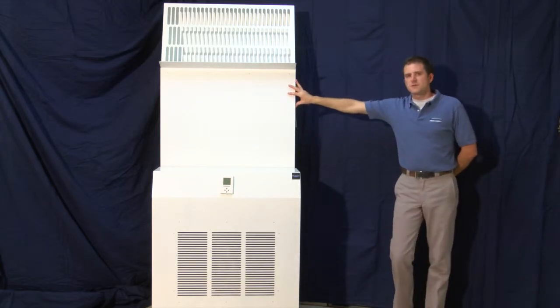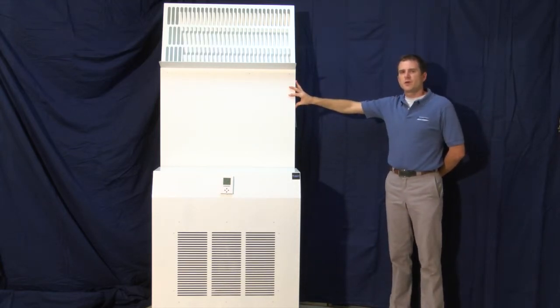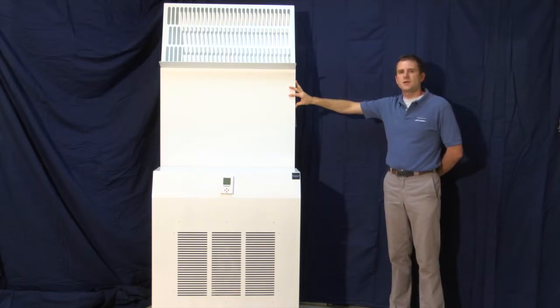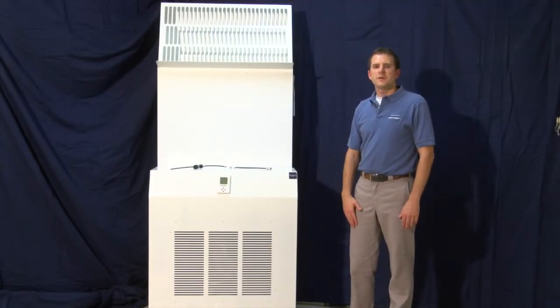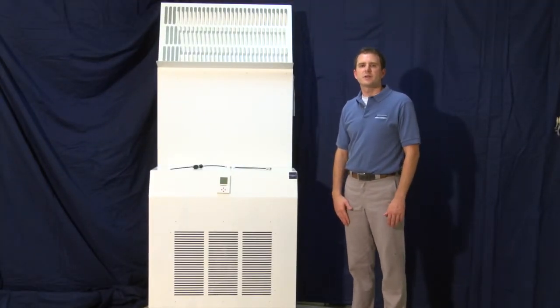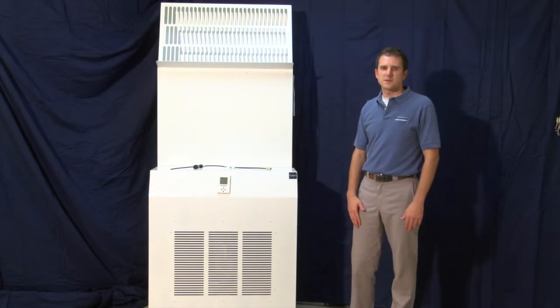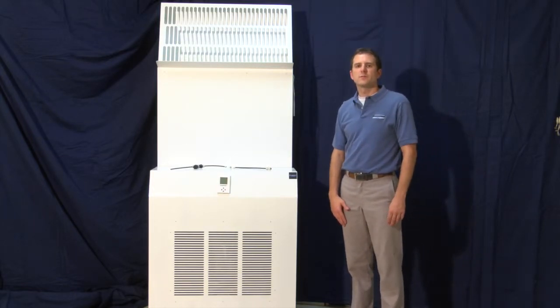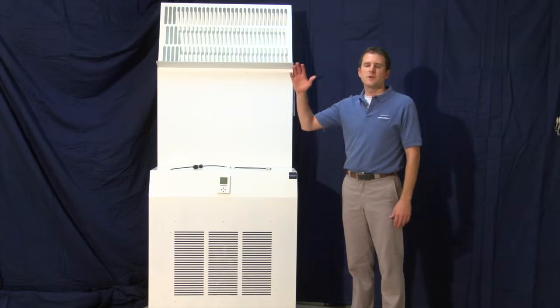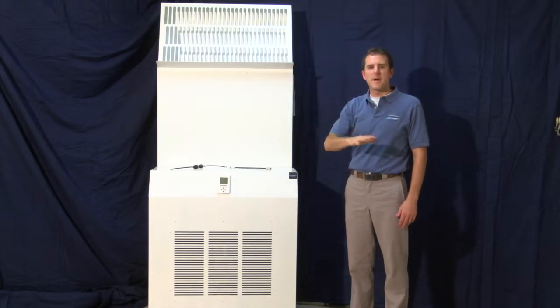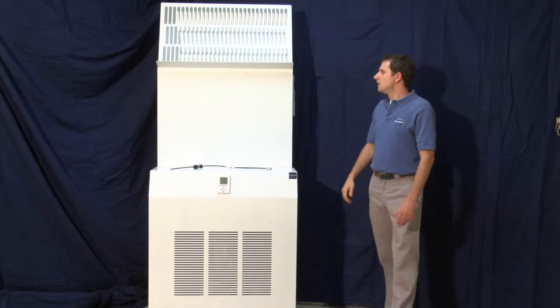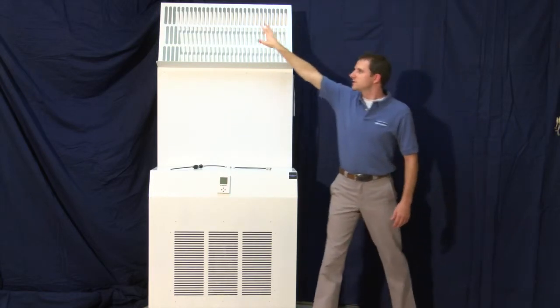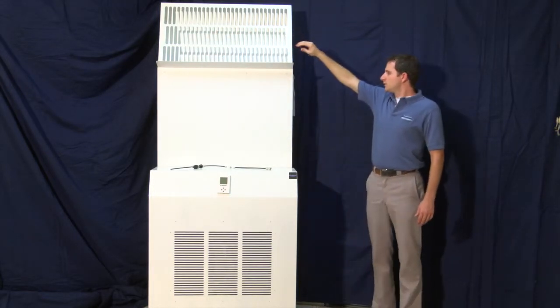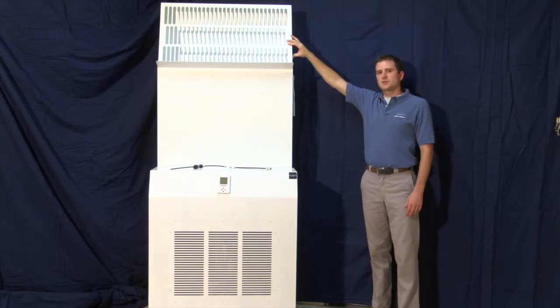After unpackaging your Mist-Free Series humidifier, simply roll it into your desired location. There are some things to think about when choosing the location of an ultrasonic humidifier. The placement of your Mist-Free Series humidifier should generally be as centralized as possible, although humidity works on pressure principles, so the higher humidity levels will automatically seek out and balance lower humidity. Most importantly, the area in front of your discharge baffle should be open and clear of any obstructions.